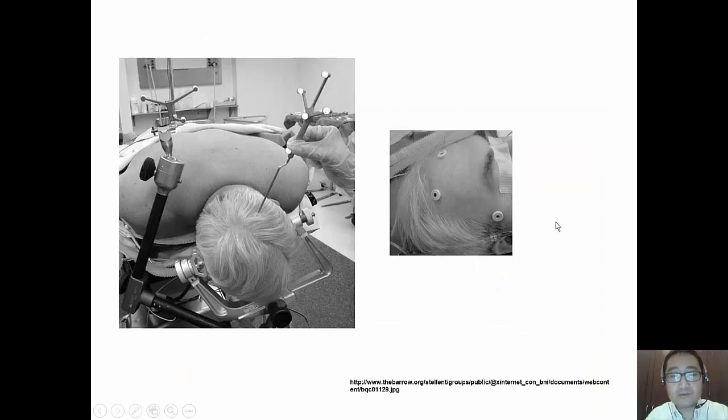In the old days, image alignment was done, and is still done in some cases, with stereotactic markers. You basically have to drill a hole and screw some markers onto the patient, and these markers will be highlighted on the images that are acquired. Then by comparing those marker locations, you'll be able to derive a coordinate transform that will bring the images into alignment.